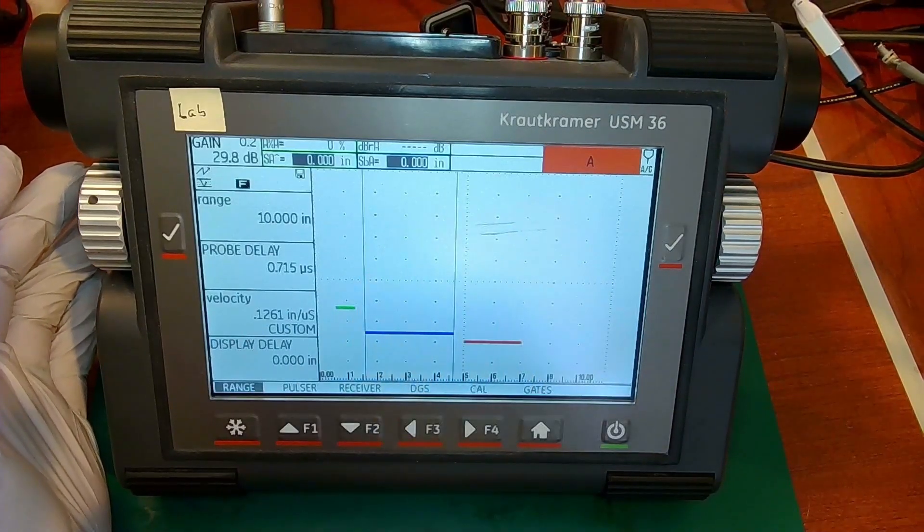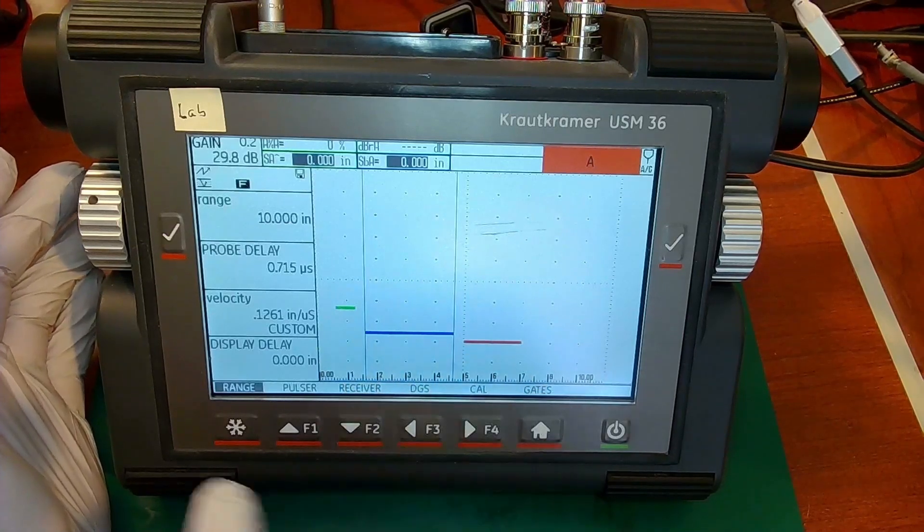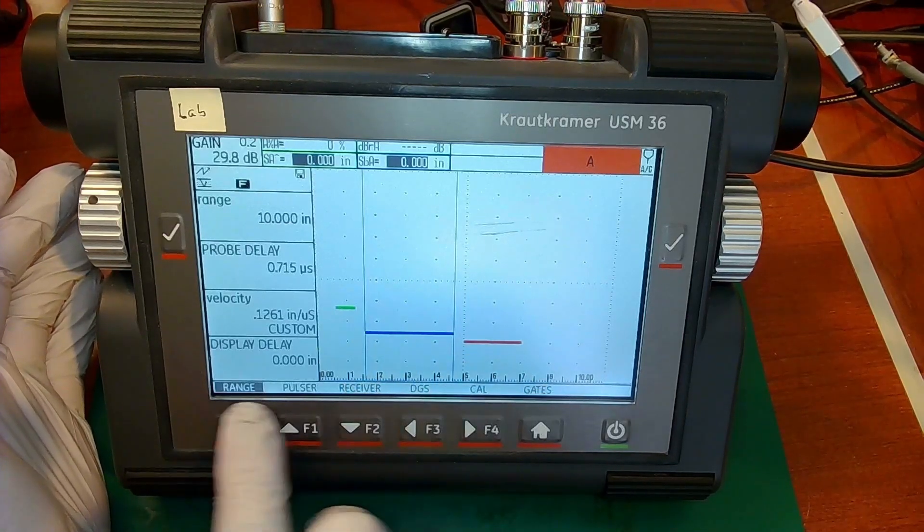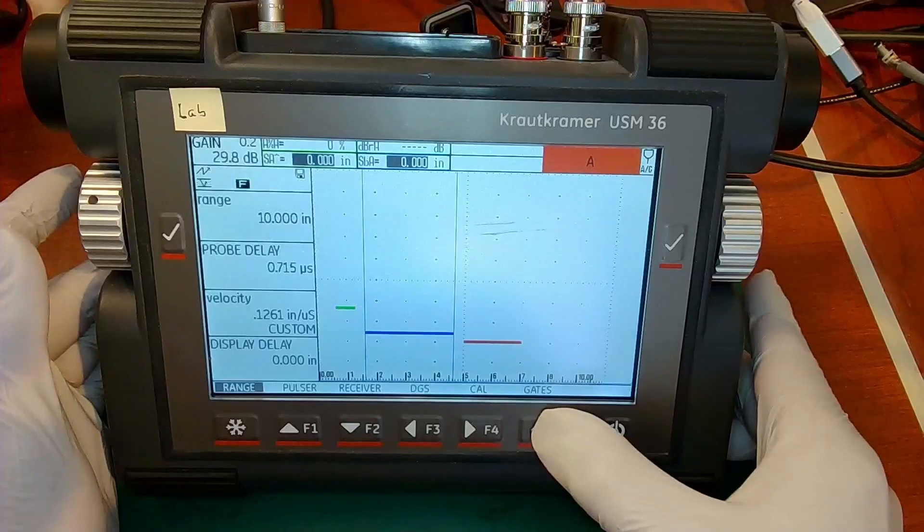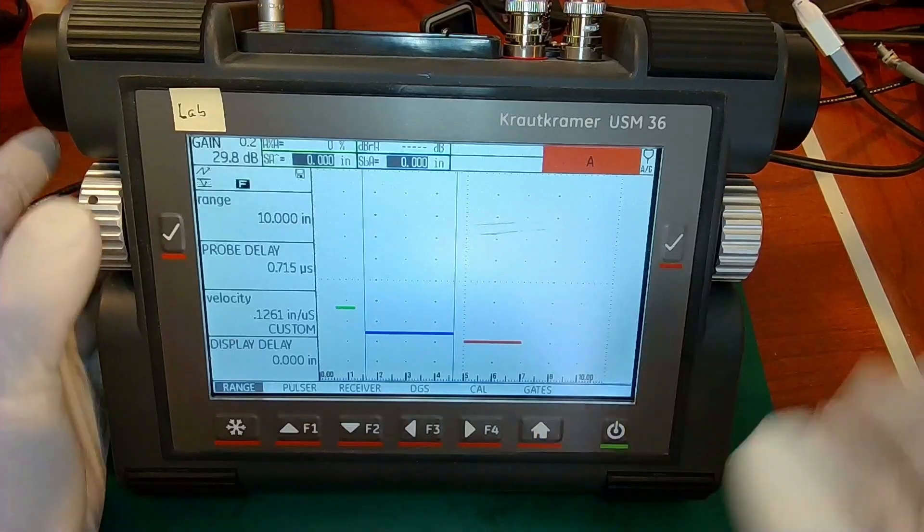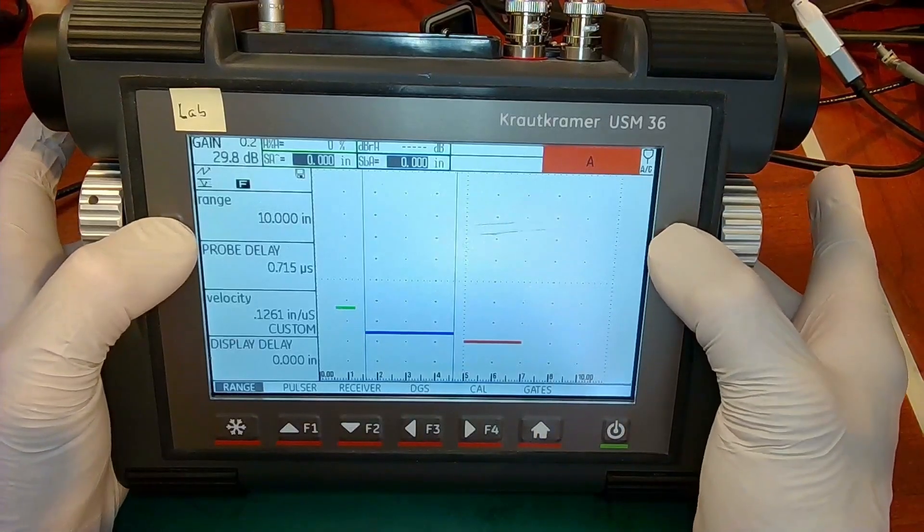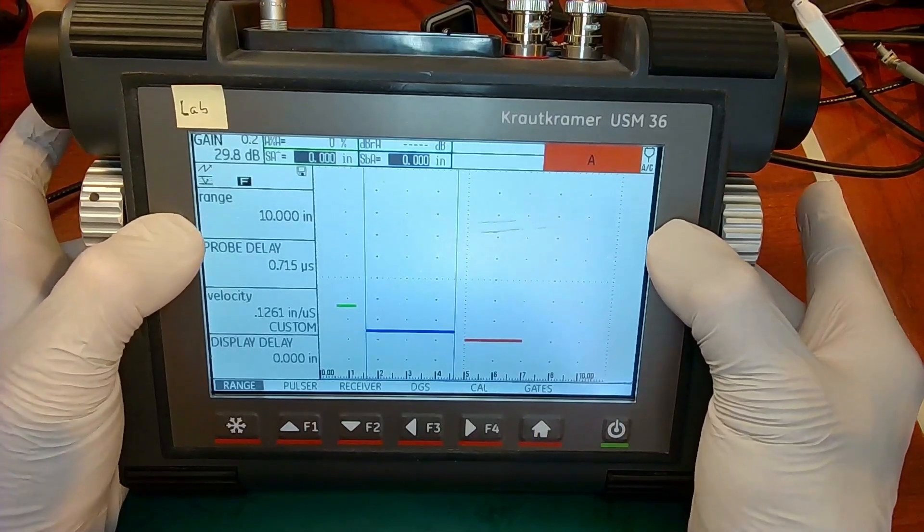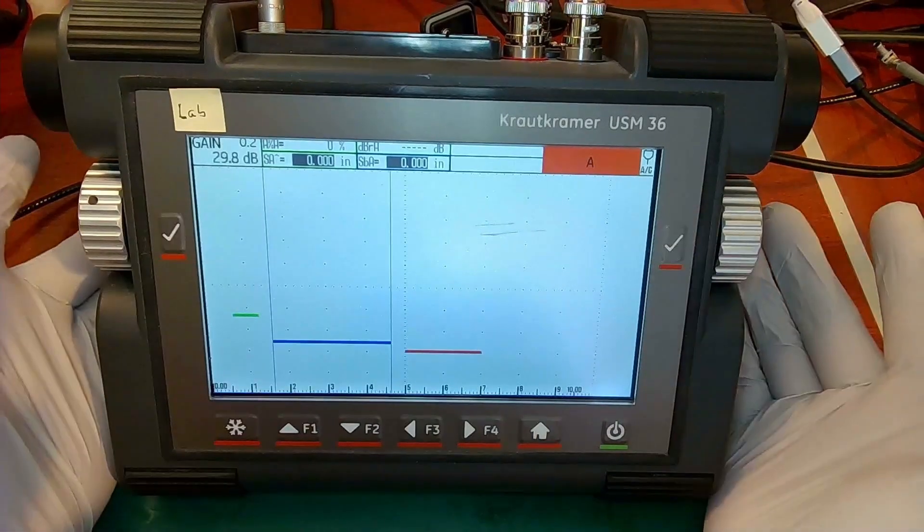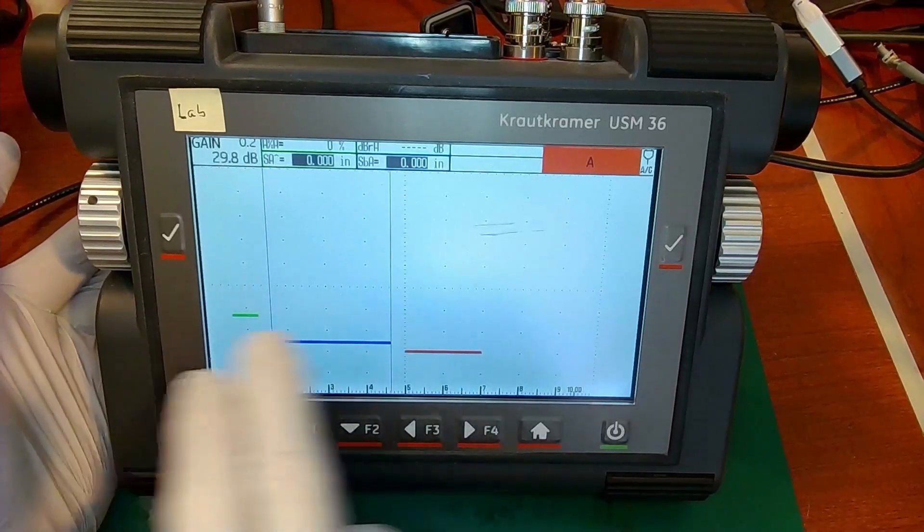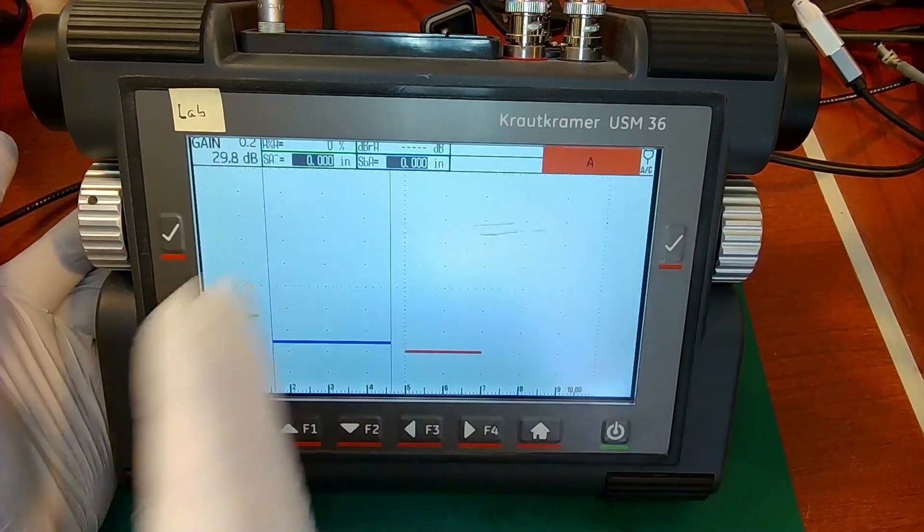Sometimes you'd like to see the A-scan large and full screen. Right now we're in the home mode. So we're down at our menu bar. If I hit both of the check marks at the same time, it will expand the A-scan to full screen. So I'll see my readings at the top and I will see the A-scan more or less full screen. The menus are hidden.